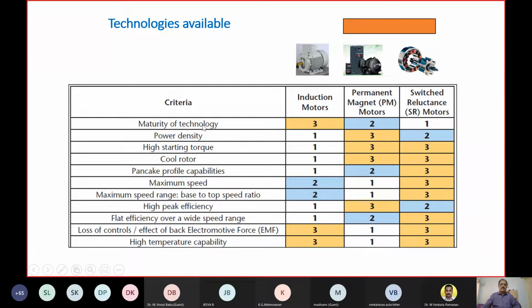Now, if you take a look at the technology per se, as we originally discussed, the most matured in terms of technology on a scale of 1 to 3 is the induction motor, followed by permanent magnet motors, and then the switched reluctance motors. And in terms of high peak efficiency, induction motors offer you the lowest among the 3 to meet the challenging efficiency levels, including part load efficiencies, while permanent magnet or switched reluctance could be leaders in order to offer you higher efficiencies. So the future of IE4 motors or IE5 motors, greater than IE4 motors, will be permanent magnet or switched reluctance motors. But almost 99% of the total motor population will be asynchronous induction motors as of today.